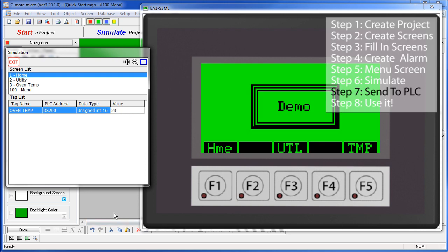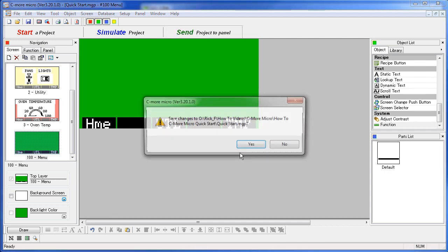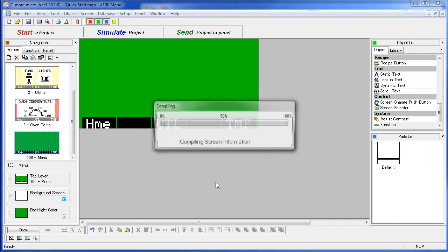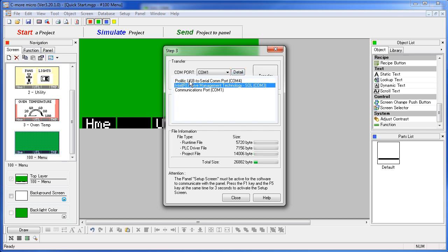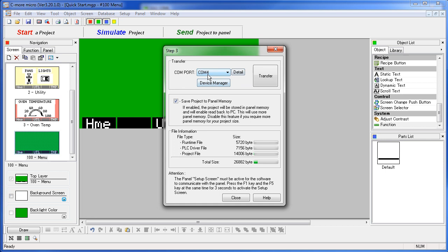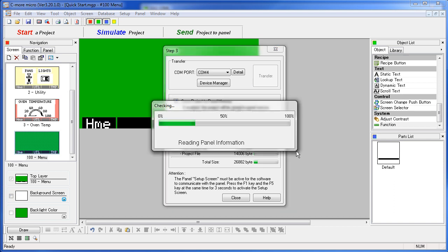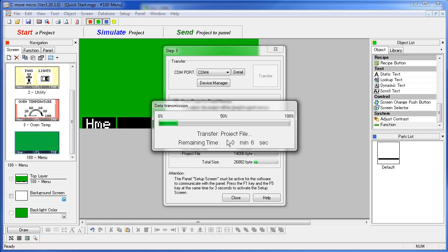Once you are happy with the way your project is working, step 7 is to send it to the panel. Click the send button, save the changes, then check your COM port. I hit the detail button to find which port my cable is plugged into – I am using this Prolific cable on COM4. I double click that and it fills in COM4. Then I hold down F1 and F5 for a couple of seconds to put the panel into setup mode. I hit transfer and the software sends the project down to the panel – first the runtime file, then the project files, so I can retrieve, edit and reload them later. The project is now on the panel, ready to go.